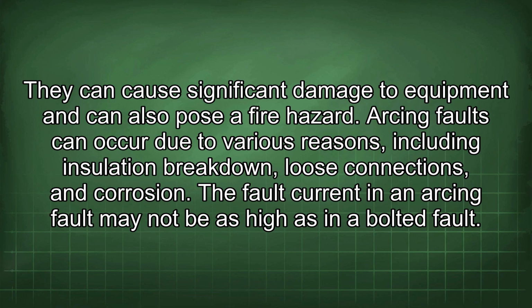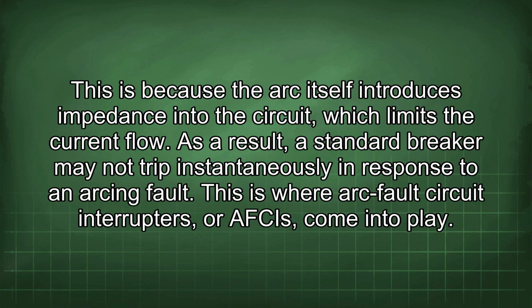Arcing faults can occur due to various reasons, including insulation breakdown, loose connections, and corrosion. The fault current in an arcing fault may not be as high as in a bolted fault. This is because the arc itself introduces impedance into the circuit, which limits the current flow. As a result, a standard breaker may not trip instantaneously in response to an arcing fault.